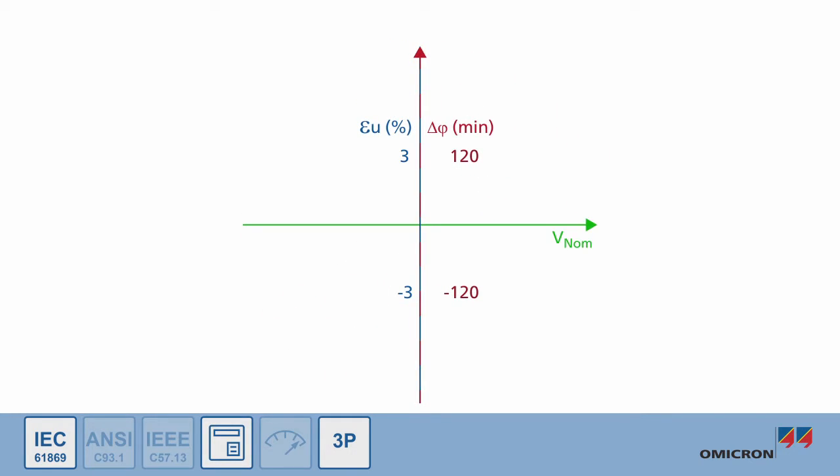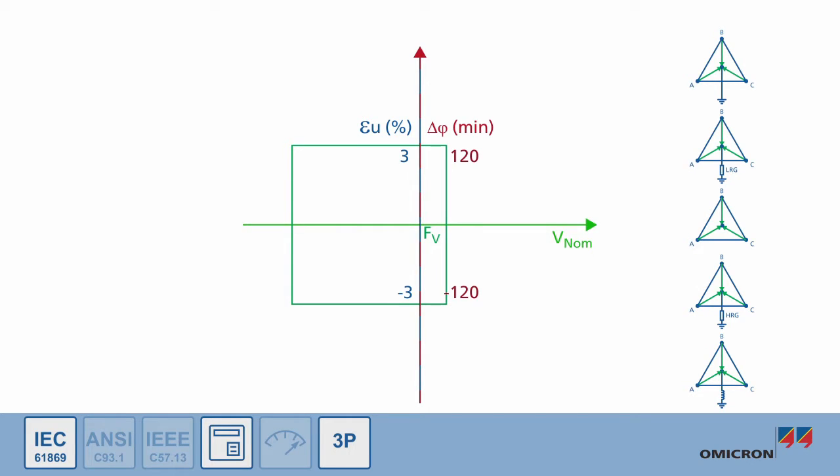The operating range is limited by undervoltage and overvoltage conditions. The upper limit of the operating range is an overvoltage that is defined by nominal voltage times the rated voltage factor. Depending on the system grounding and the applied earth fault protection, typical rated voltage factors are 1.2, 1.5, and 1.9.